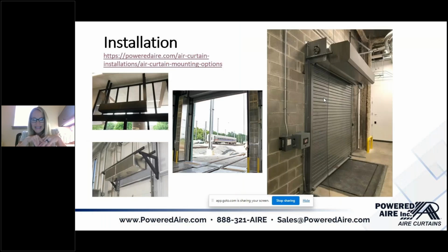Here's just some other examples of installations. Top left, they did threaded rod, but then they wrapped it so it matched the entryway. Tons of different brackets. The picture in the center is actually two vertically mounted air curtains. That is an option. We always try to go overhead if possible. Sometimes it's just not an option, so we can do vertically mounted. If you are choosing this installation style, let us know at the time of design. We need to put special supports on the motor mounts.